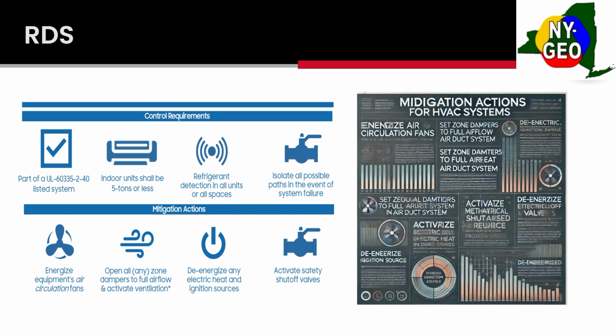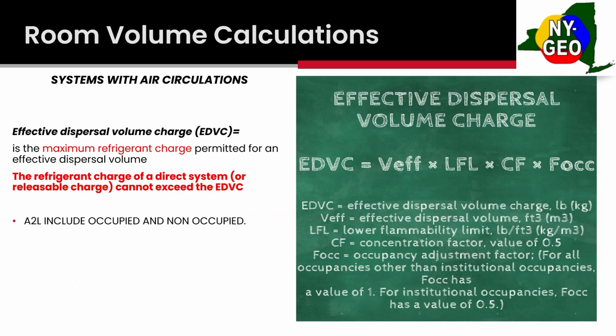All right, so here's the real fun part. What we're going to use instead of our RCL calculations in ASHRAE 15 is now the effective dispersal volume charge, the EDVC. This is the maximum refrigerant charge permitted for an effective dispersal volume. So your refrigerant charge of a direct system, or your releasable charge, cannot exceed your EDVC. A big difference between this and A1 is that with A2L, you include your occupied and non-occupied spaces in your EDVC.